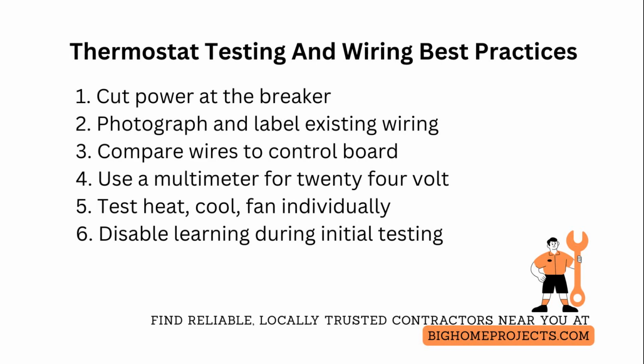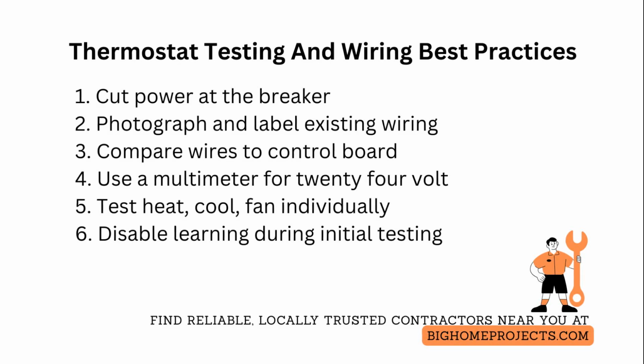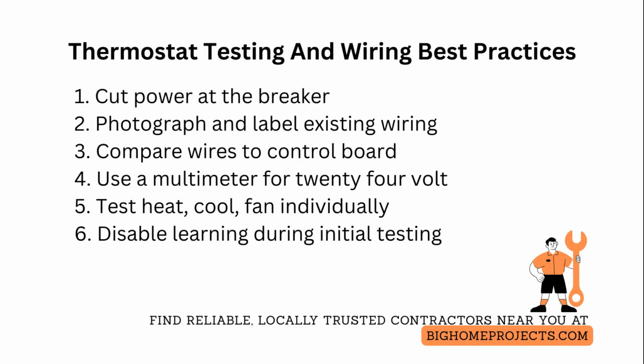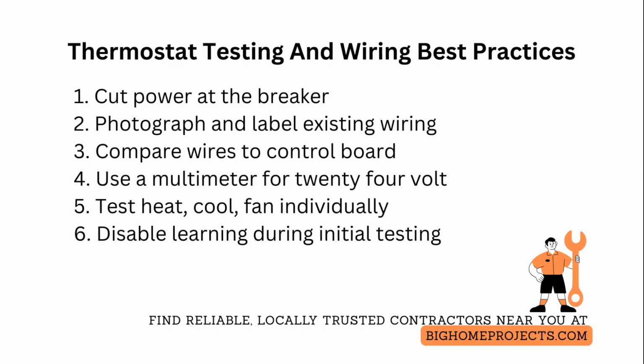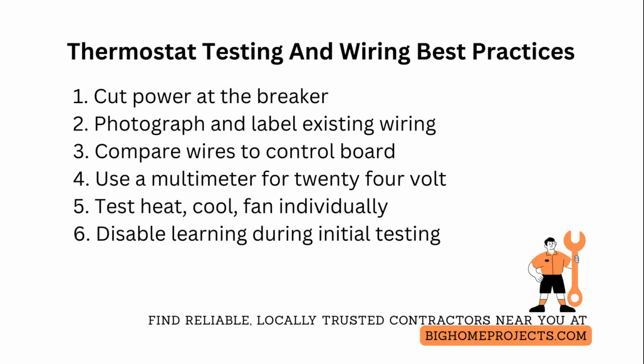After wiring, power up and run each function one at a time. Set the thermostat to heat, wait for the defined system delay, confirm the furnace ignites, and that the thermostat cycles off at the target temperature. Then repeat for cool and fan-only modes while watching for rapid short cycling, which indicates a wiring or equipment issue.